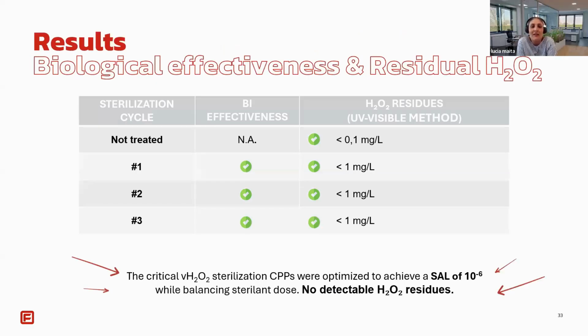So the results. The results show that across all the tested locations, biological effectiveness was achieved with no growth observed for the biological indicator after 7 days of incubation. In parallel, the residual amounts of H2O2 were consistently below 1 milligram per liter, and this result indicates that the selected process parameters allow us to balance the sterilization performance and the residual control.